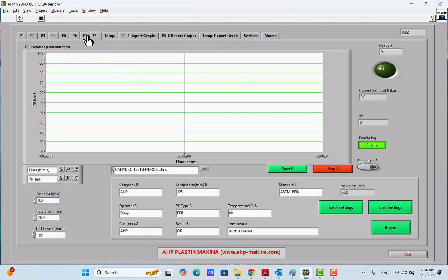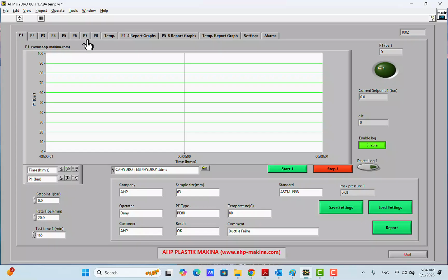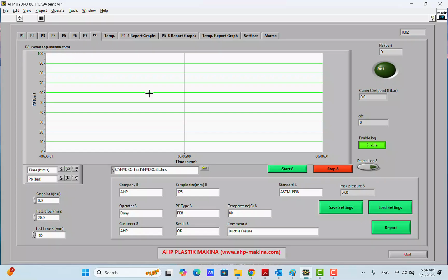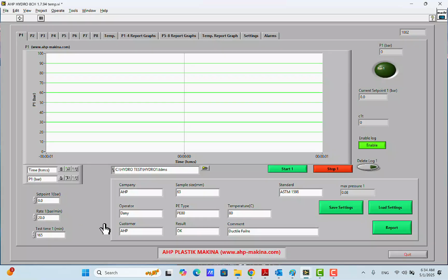The software has 8 tabs for the pressure setting of 8 channels. In each channel, you have a function for setting the set point of the pressure. Here, you have the functions in basic hydrostatic testers from AHP Plastic Makina. The pressure can go up to 100 bar, for example. You can set the set point to 100 bar. The resolution is 0.1. There are versions with the accuracy of 0.01.